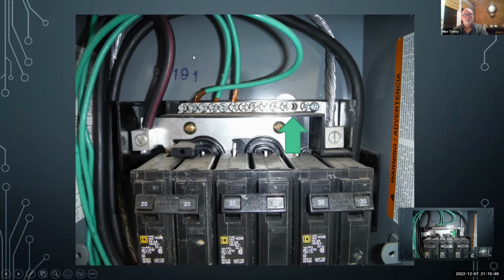This panel could be used, this could be used as a neutral bar in a different situation. That's why it's floating. In this case, there's no neutral and that should be bonding it, but this bar is not contacting this can. So all this is not bonded. This particular panel could become energized and there's no path to clear a fault on it.